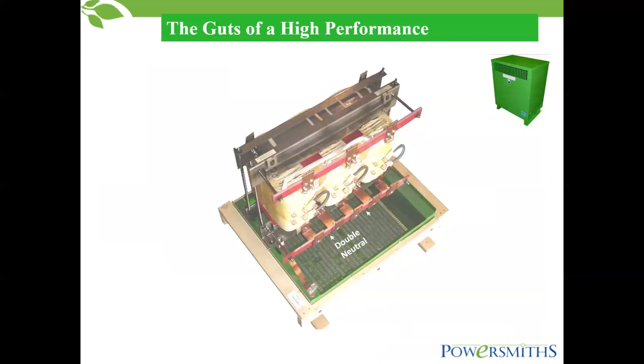So what's the guts of a high performance transformer? I already talked about the core. You're using a higher grade steel, mitered and wound, 2 to 3 times less losses than the typical transformer. You're looking at a better design. This is the typical design of Square D's and GE's and Siemens and everybody else's Cutler Hammers in the world.